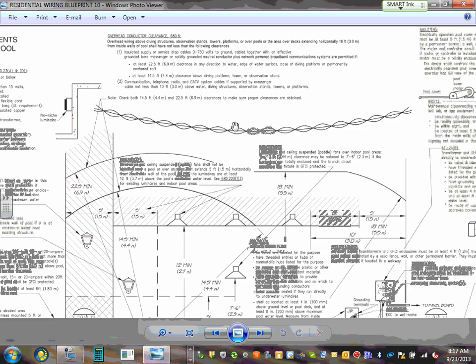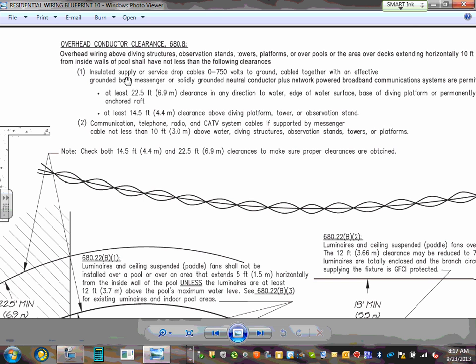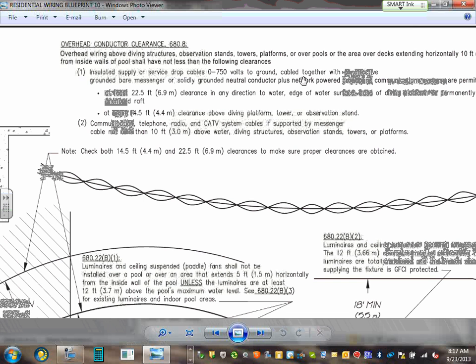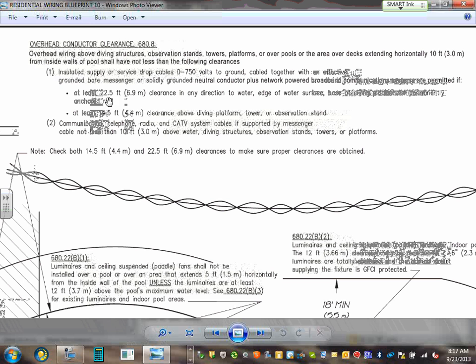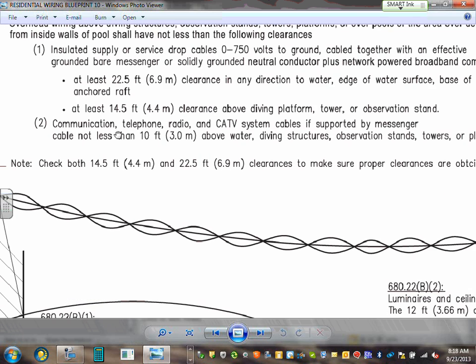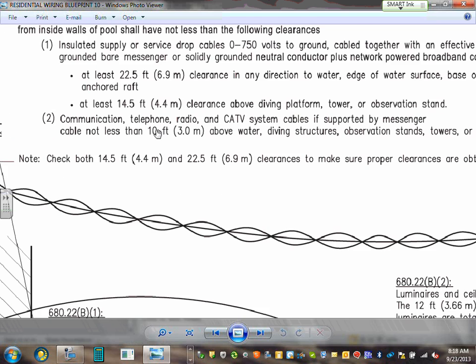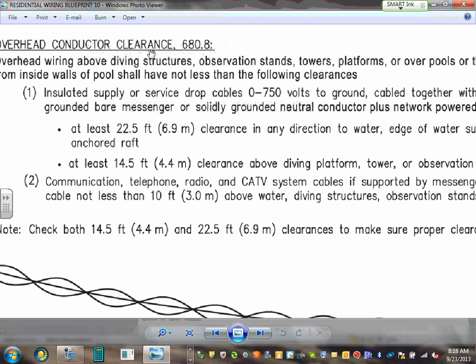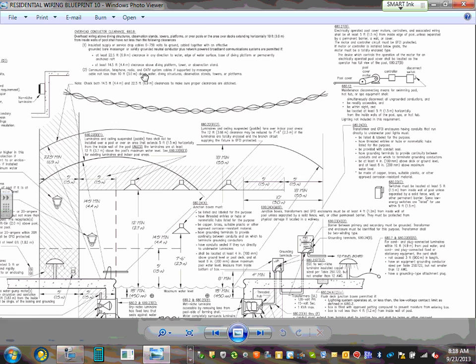Power lines, look at that. Power lines right above the swimming pool. Here are the rules for the power lines. Insulated supply service drop from this voltage to this voltage, and so on. Look at that. At least 22.5 feet clearance in any direction to the water edge, platform, and everything else. If you were to bring the power over your swimming pool, or if your neighbor decided to dig a swimming pool right under the power lines, make sure they're clearing it with 22.5. Remember, the code requires only 10 for the power lines. Now you're getting 22.5. Communication lines. If you have a communication line, what's the number? 10. You have to clear by 10. So these are the rules for the power lines. Okay, moving on. We got that one.